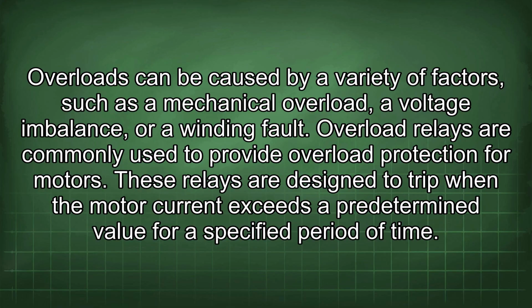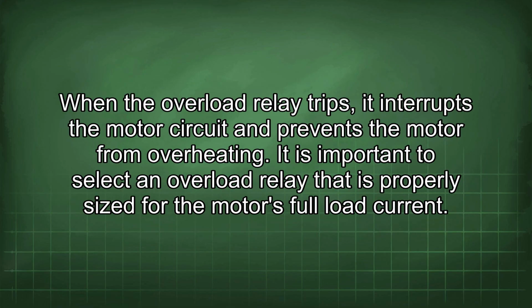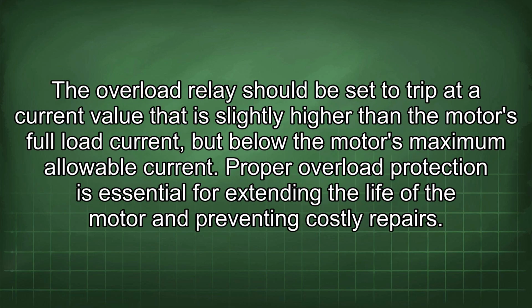These relays are designed to trip when the motor current exceeds a predetermined value for a specified period of time. When the overload relay trips, it interrupts the motor circuit and prevents the motor from overheating. It is important to select an overload relay that is properly sized for the motor's full load current. The overload relay should be set to trip at a current value that is slightly higher than the motor's full load current, but below the motor's maximum allowable current. Proper overload protection is essential for extending the life of the motor and preventing costly repairs.